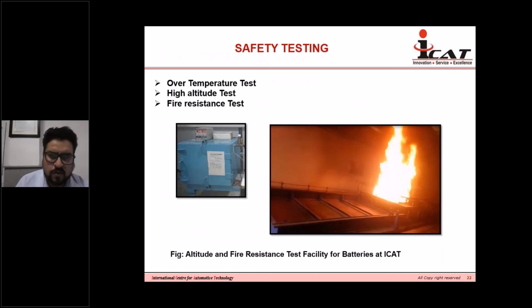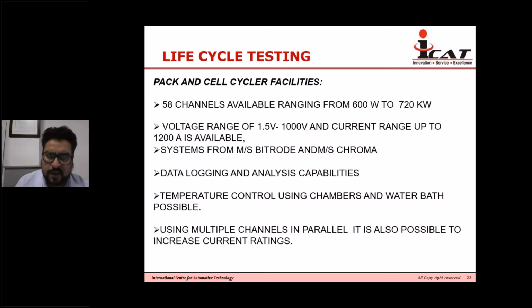Life cycle testing of batteries is something we can perform at ICAT. We have increased our capacity to almost 60 channels now, and can go from as low as 600 watts, good for a small cell, right up to 720 kilowatts, with a voltage range of 1.5 volts to 1000 volts, and current up to 1200 amperes.